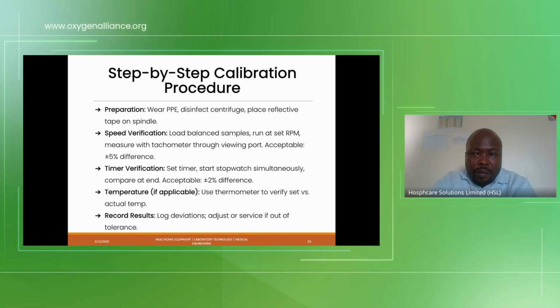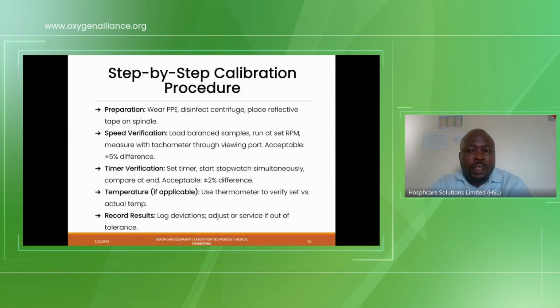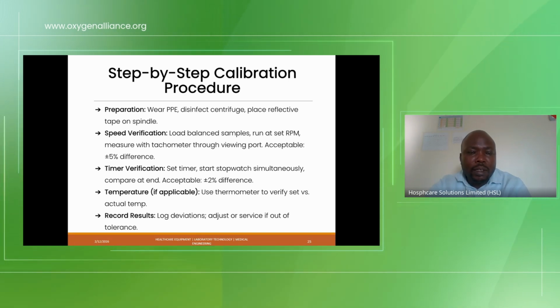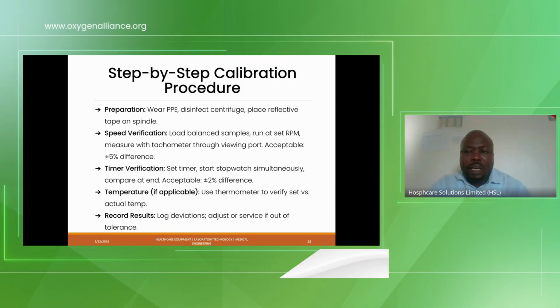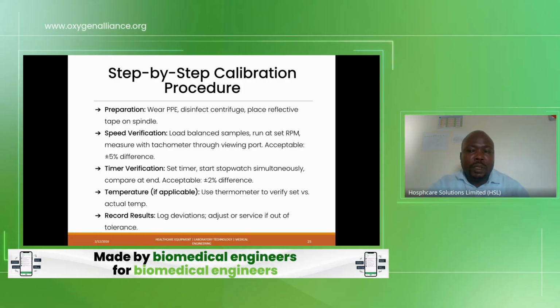Okay, we go for speed verification using a tachometer. You measure the rotor speed with a digital tachometer. So how do you do it? You start by setting a test speed. You can choose common speed figures, 1,000, 3,000, or 5,000 revolutions per minute. You run the centrifuge at each speed, then measure and record. You compare the readings and check whether the measured revolutions per minute match the set revolutions per minute on the machine. If they don't, you can calculate the error as a percentage.